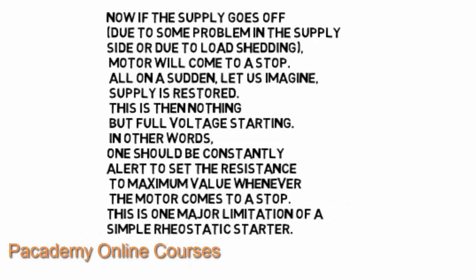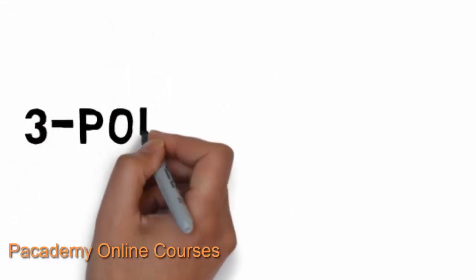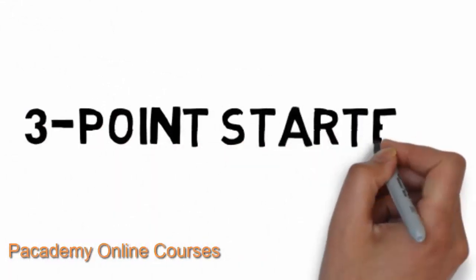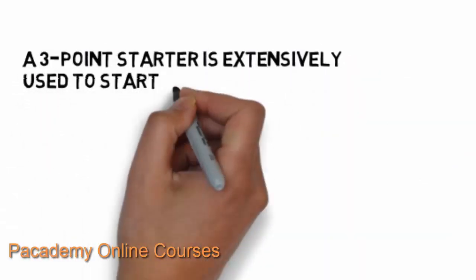One drawback of this simple starter is that if the supply goes off due to a problem on the supply side or load shedding, the motor comes to a stop. If the supply is then restored, it applies full voltage immediately, causing high starting current again. The operator must be constantly alert to reset the resistance to the maximum value whenever the motor comes to a stop. This is a major limitation of the simple rheostatic starter.